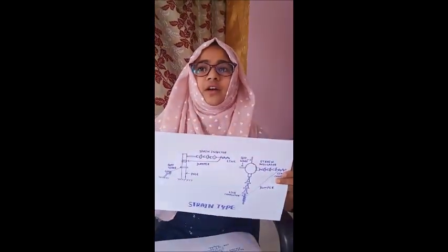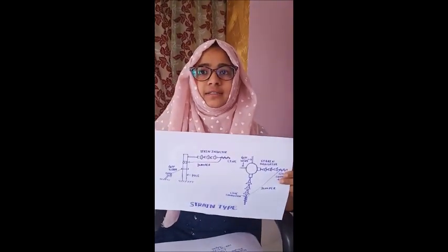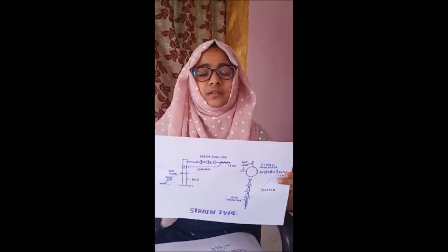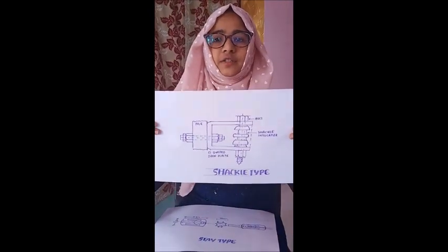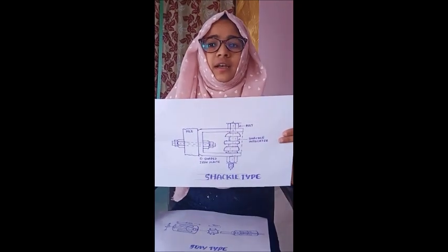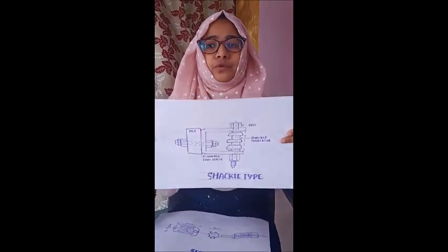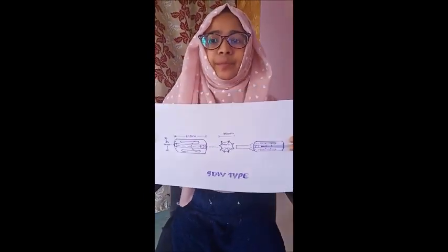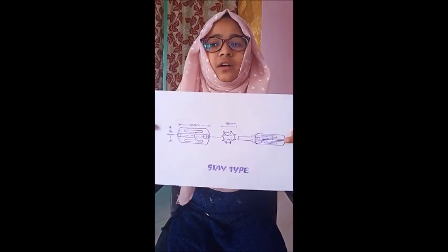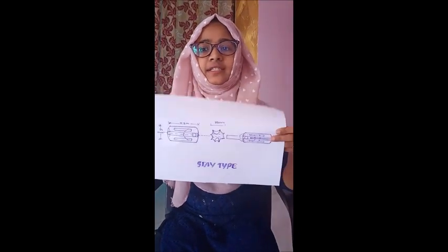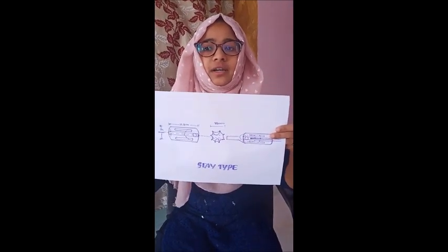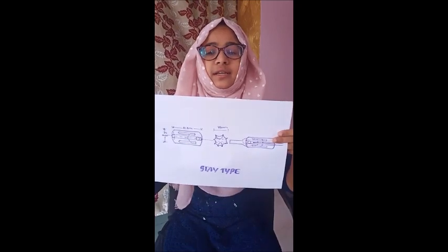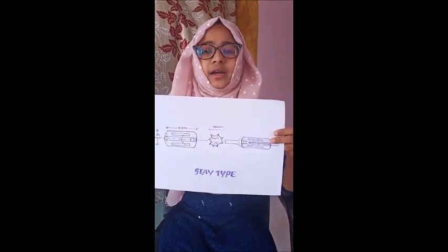Third is strain insulator, used when there is a dead end of the line, or the line is at a sharp curve, or crossing a river. Fourth is shackle type insulator, also called spool insulator, used for low voltages. These can be used in horizontal or vertical positions and are round in shape. Fifth is stay type insulator, also called egg type insulator. In case of low voltage lines, stays must be insulated at a height of not less than 3 meters. These are used with stay clamps to create insulation.